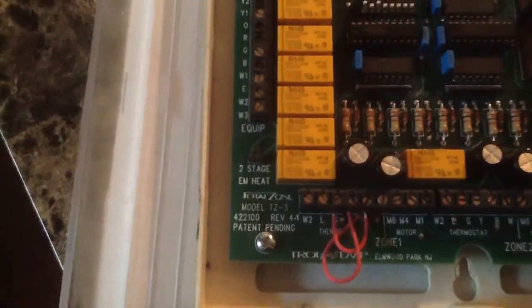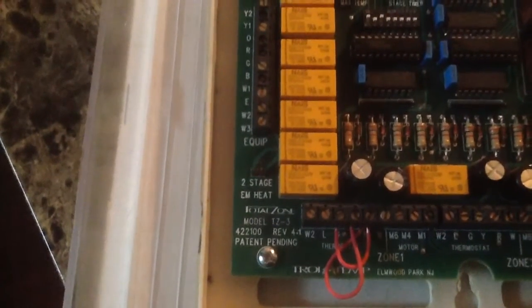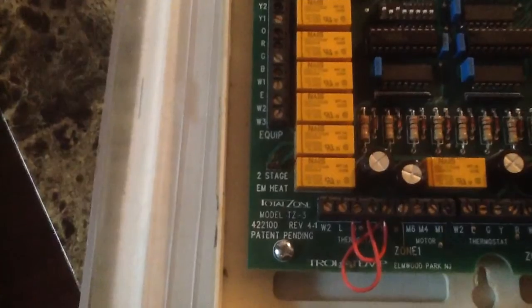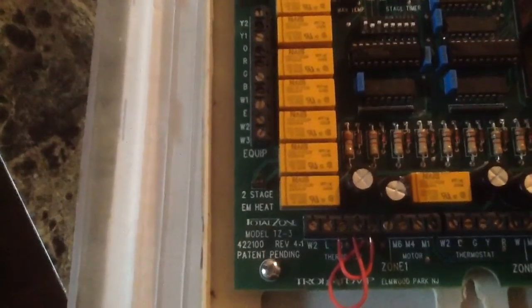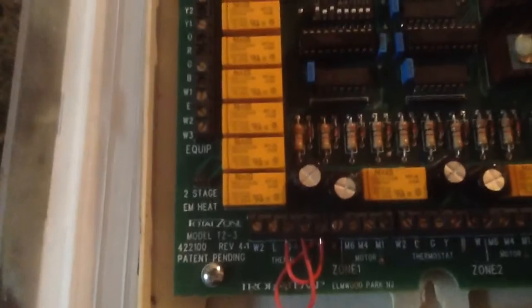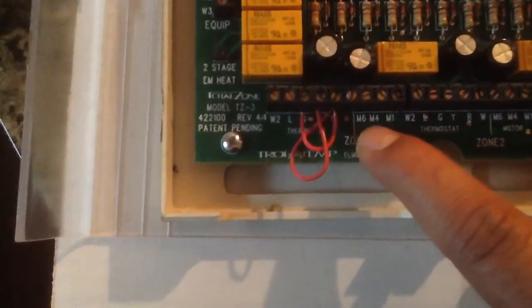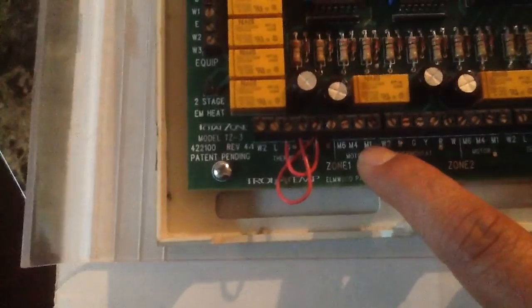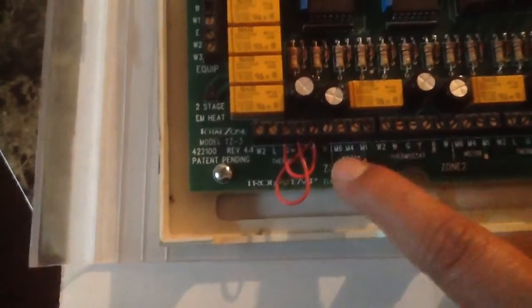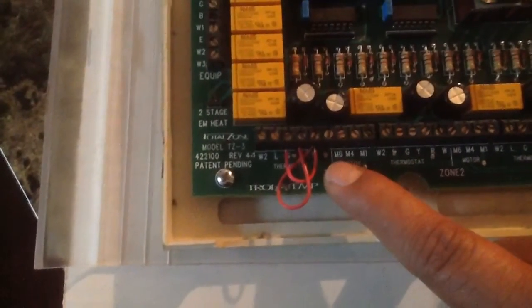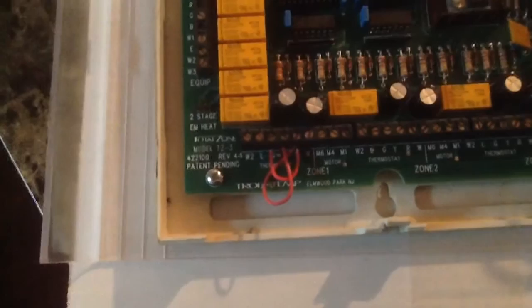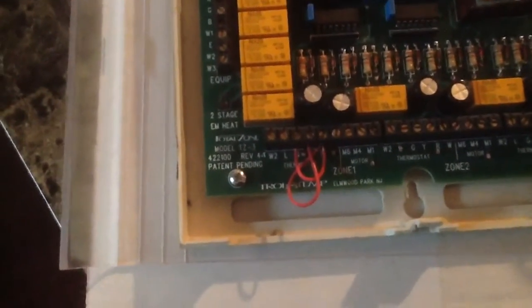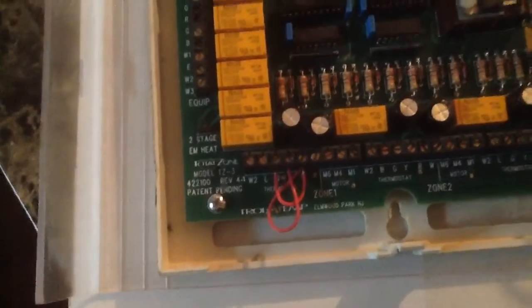So your thermostat for the zone 1 area will be wired into the terminals here. This one, you can run 2-stage equipment on there, or a 2-stage thermostat as well. And on the right side you got your motor over here, and you'll see there's an M6, M4, M1. M1 typically is going to be your common, M4 if I'm not mistaken is open, and M6 is your close. And that's powering up your motor, whether it's a power open spring close motor, or a power close spring open motor, or power open power close motor.